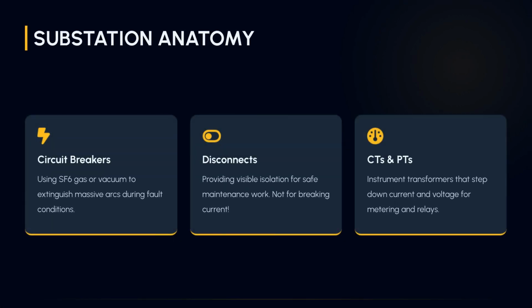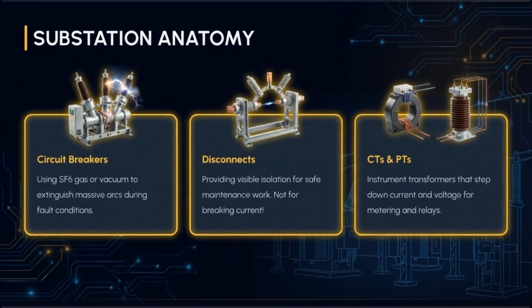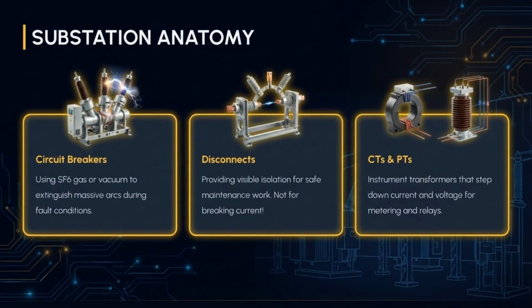Substation components are essential for protection and control. Circuit breakers use gas or vacuum to extinguish arcs. Disconnects provide visible isolation for safety. CTs and PTs, instrument transformers, step down current and voltage for metering and relays. This image highlights the critical components within a substation, demonstrating the mechanisms used for current interruption, safe isolation, and precise measurement within the high-voltage environment.